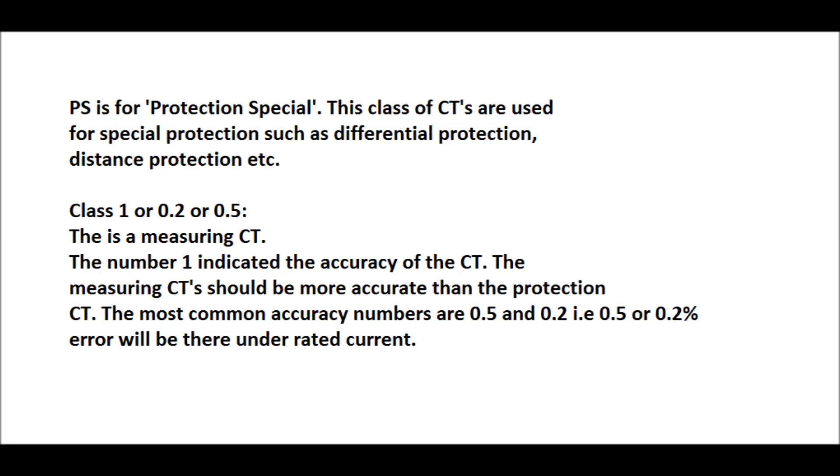There are another class that is class 1 or 0.2 or 0.5. This class is a measuring CT used for metering purpose. The number 1 indicates the accuracy of the CT. In case 100% that is rated current flow, the error shall be 1%. In case of 0.2, the error shall be 0.2%. In case of 0.5 class, the error shall be 0.5%.